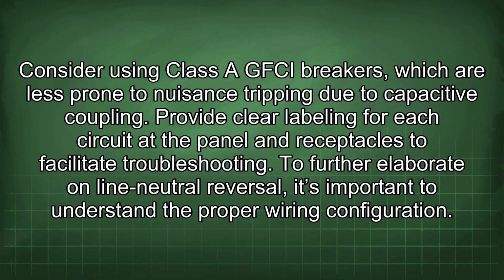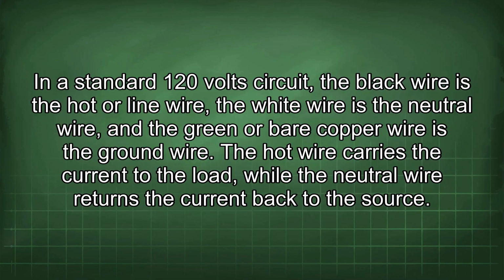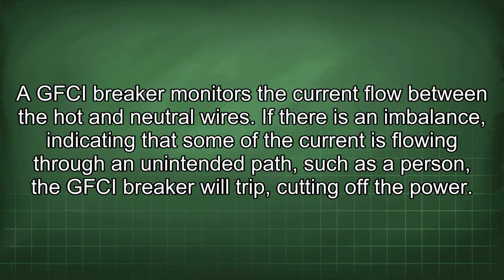To further elaborate on line neutral reversal, it's important to understand the proper wiring configuration. In a standard 120-volt circuit, the black wire is the hot or line wire, the white wire is the neutral wire, and the green or bare copper wire is the ground wire. The hot wire carries the current to the load, while the neutral wire returns the current back to the source. A GFCI breaker monitors the current flow between the hot and neutral wires. If there is an imbalance, indicating that some of the current is flowing through an unintended path, such as a person, the GFCI breaker will trip, cutting off the power.